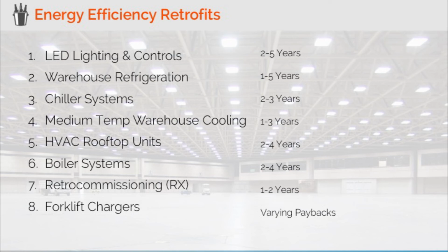As for comfort heating and cooling, the same goes for package heating and cooling rooftop units for offices and other areas. Once assessed, these units should be retrocommissioned if they're over a few years old. In the event that they are at the end of life, the efficiency of replacement units coupled with utility incentives could make for attractive paybacks on the new equipment.